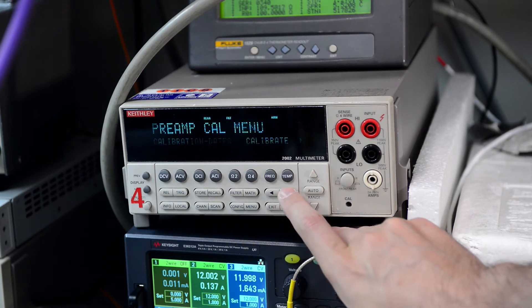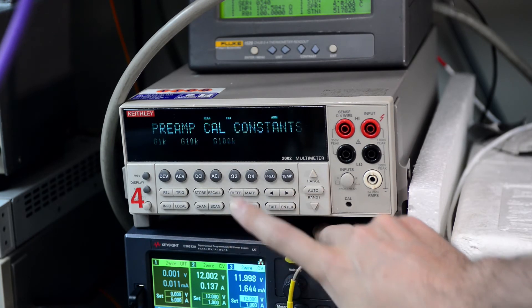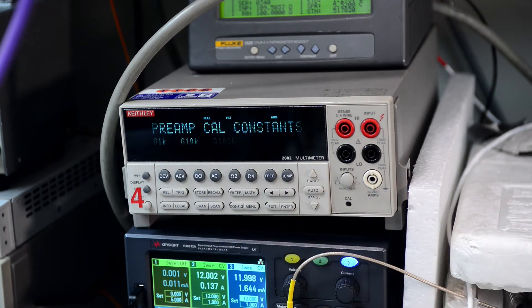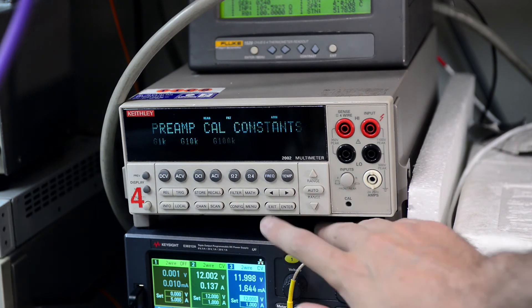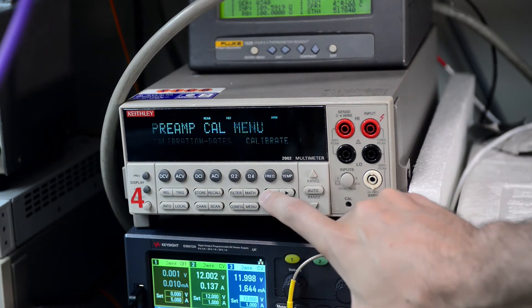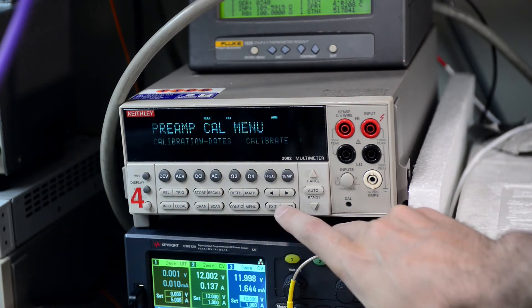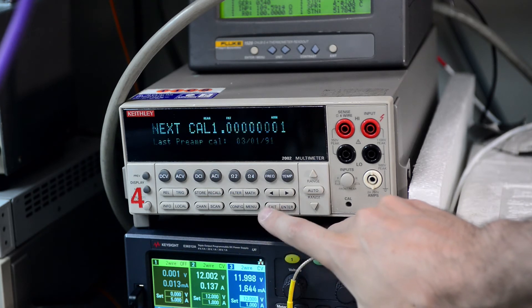And exactly the same happens if I try to enter the calibration constants through GPIB or front panel, there is no difference. And this meter is running firmware version A10. This is the latest for A series.